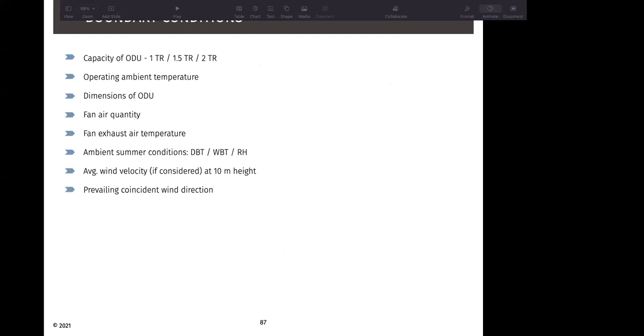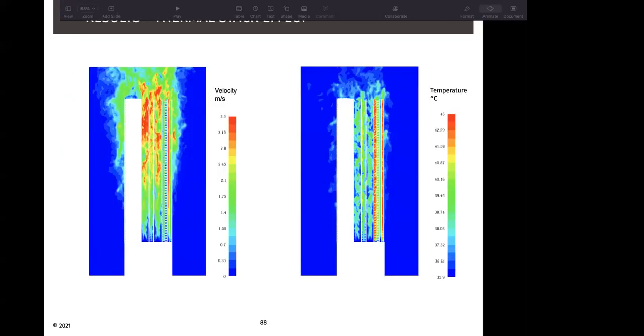Again, looking at the boundary conditions, we have the operating ambient temperature, the dimensions of the ODU, the fan air quantity, the fan exhaust temperature, the ambient summer conditions for that particular location, average wind velocity, and the prevailing coincident wind direction. What we can see is that for this particular high rise, if the ODUs are all working, all 1776 ODUs in 23 shafts, we would see in a no wind condition there would be an updraft of air due to thermal stacking.